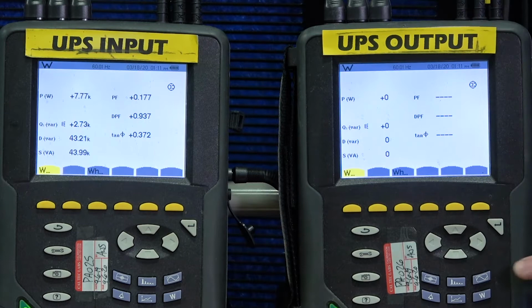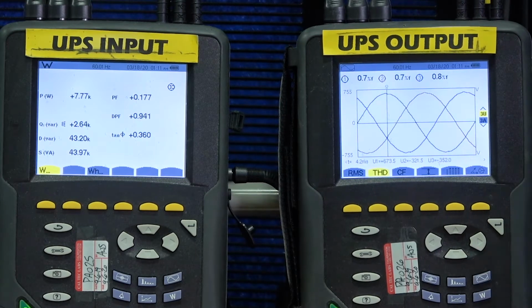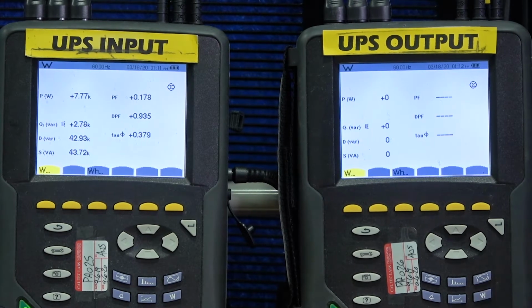Another thing that's interesting to see is the overall harmonic content of the UPS output waveform voltage. Currently, on each of the 3 phases, we have about 0.7, 0.7, and 0.8% total harmonic content of the UPS output voltage waveform. So we're now going to increase the load to 25% and show you the losses of the UPS at 25% load.